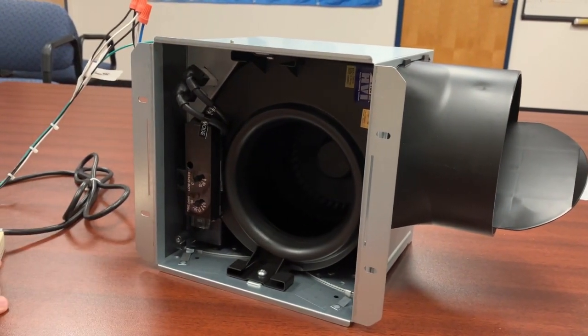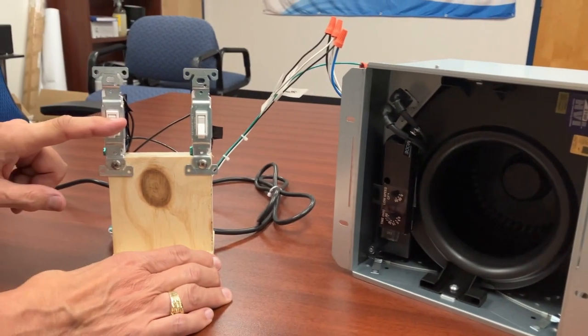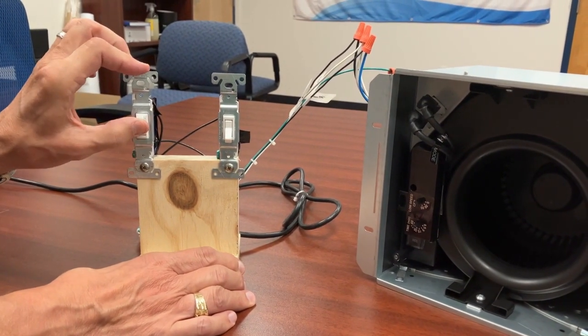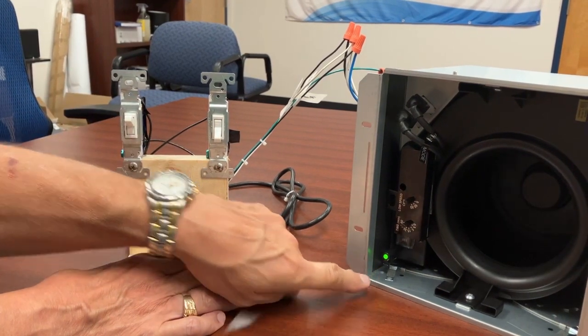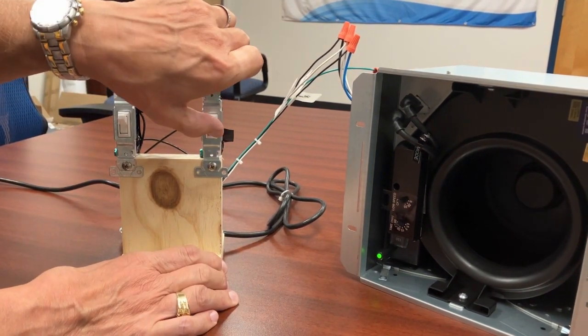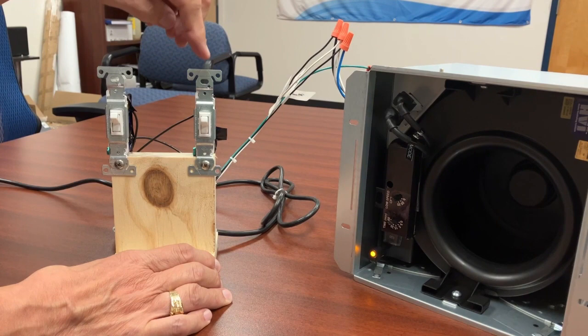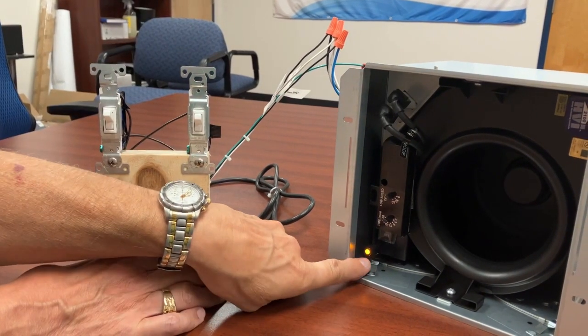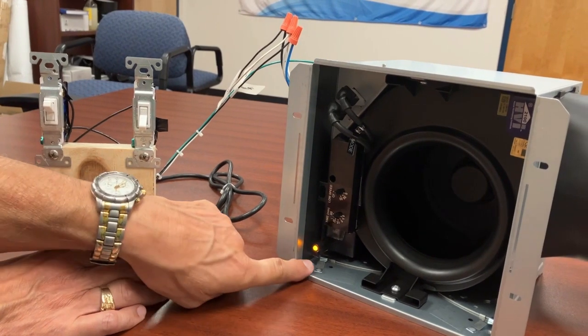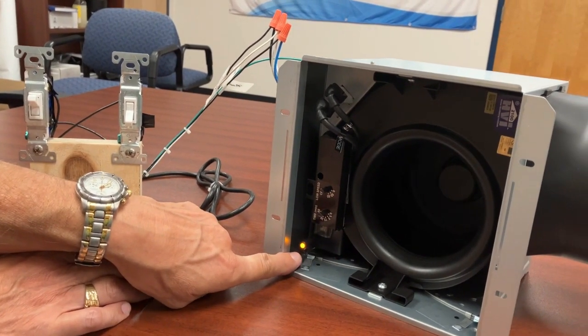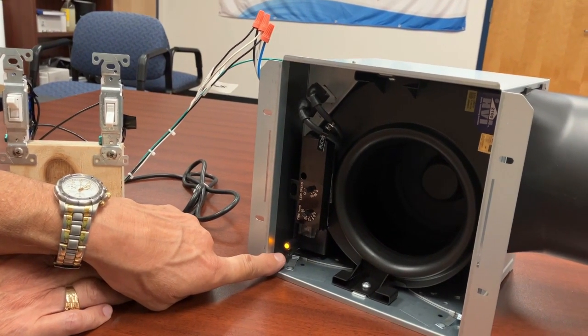So you have your disconnect, which puts it in the background. The switch must be on, so it's running its background. And this switch controls the boost and the low flow. In the on state, we're in boost. In the off state, after the delay is satisfied, it will go back to background.